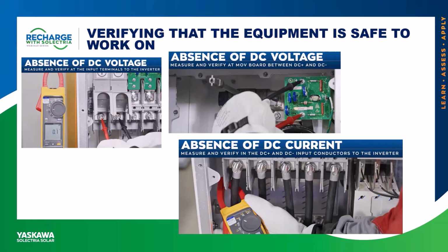So we want to make sure that we check everything. And like I said before, inside we've got a capacitor bank. So when you shut the DC off, the PV array, you disconnect it, all you're doing is removing the voltage that goes to those inside the unit. You still have, from that switch back out, just like that picture shows, you might still have voltage there. So just because you shut a switch off, don't take anything for granted. You've got to check everything.